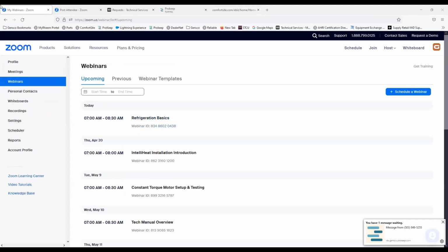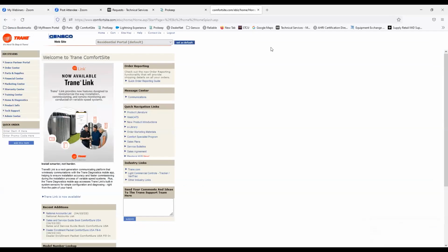So we would prefer you to start the equipment and charge by subcooling or by the service facts. And the other reason is that if you put a bunch of refrigerant into your line set and then you open it up, you're washing out a lot of the oil. So we prefer you not to do that. We don't want you to wash the oil out of the equipment. So it's better not to do if we can get away from it.